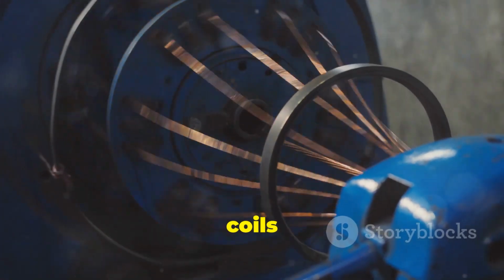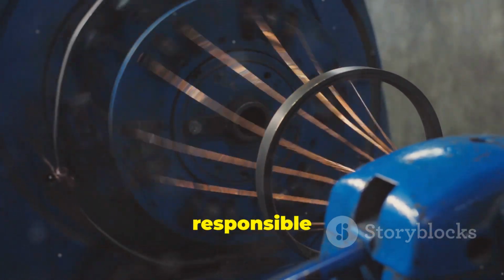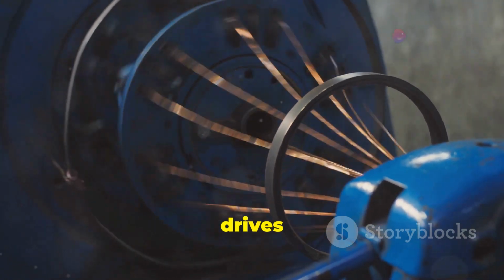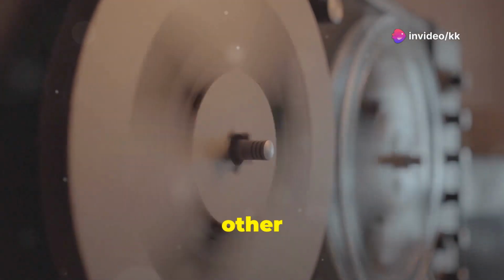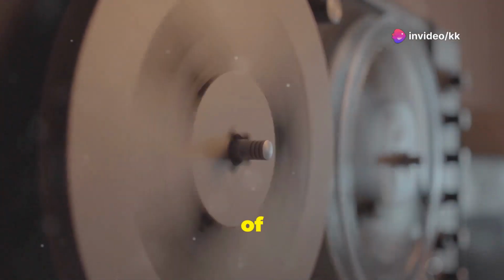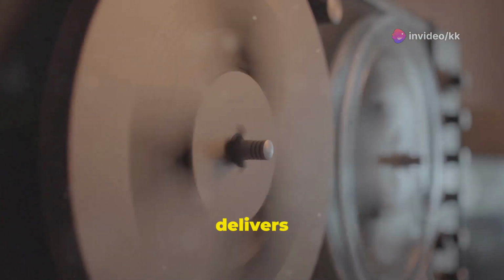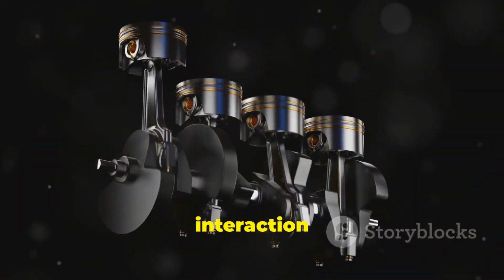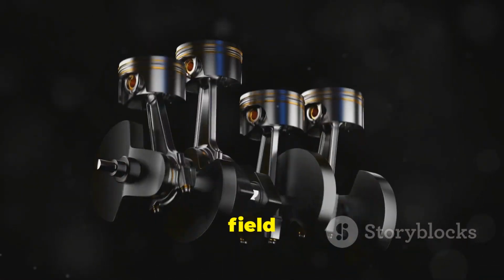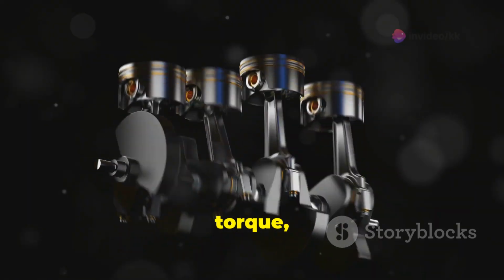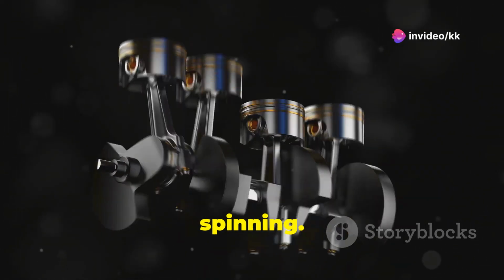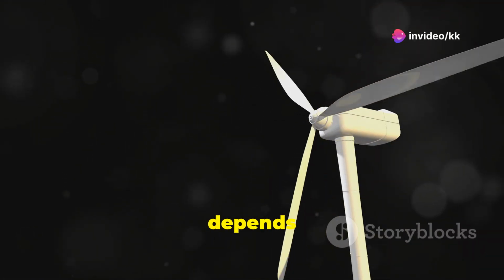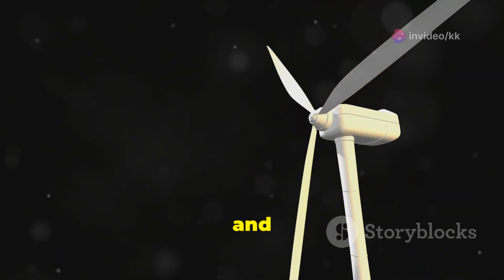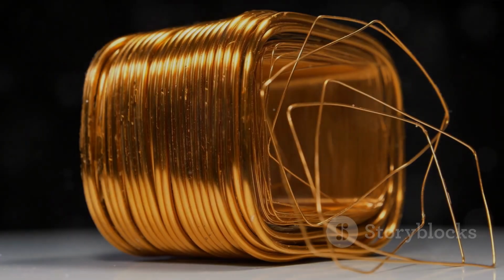The stator is the stationary outer part of the motor, typically mounted to a rigid frame. It houses coils of wire called windings, which are responsible for creating the magnetic field that drives the rotor's rotation. The rotor, on the other hand, is the rotating inner part of the motor, connected to the shaft that delivers the mechanical power. The interaction between the stator's magnetic field and the rotor's induced current creates a torque, or a turning force, that sets the rotor spinning. The speed of this rotation depends on the frequency of the AC supply and the number of poles in the motor's design.